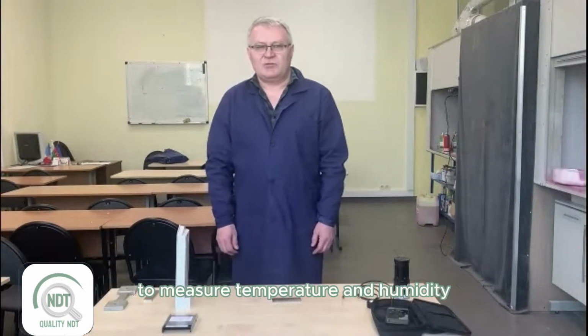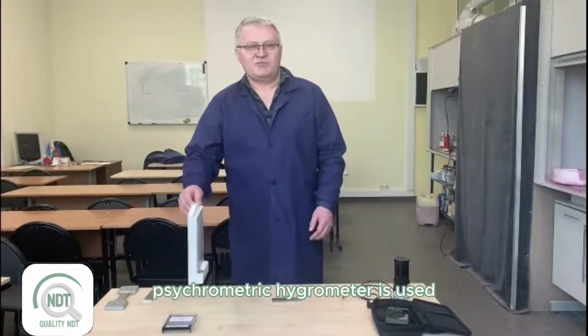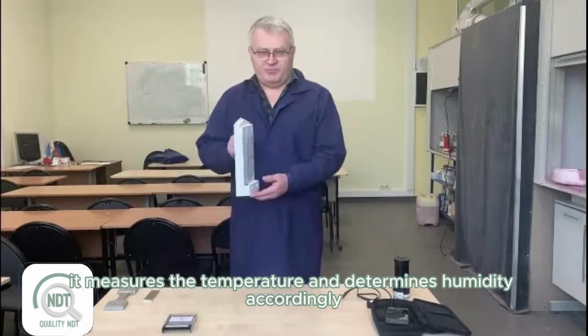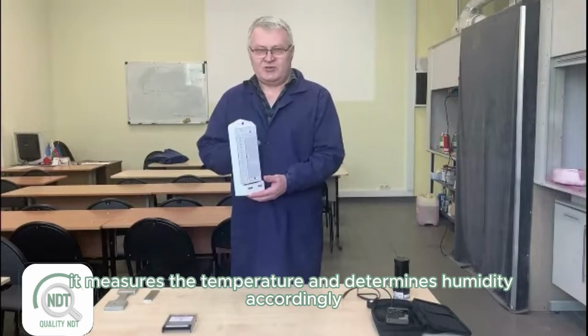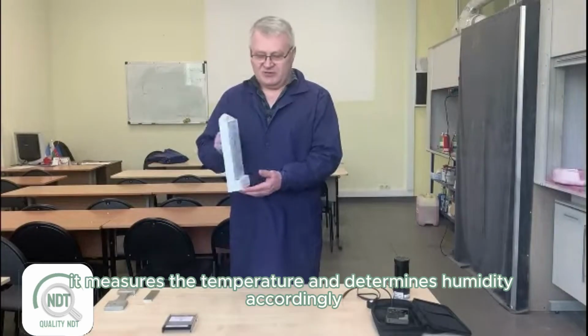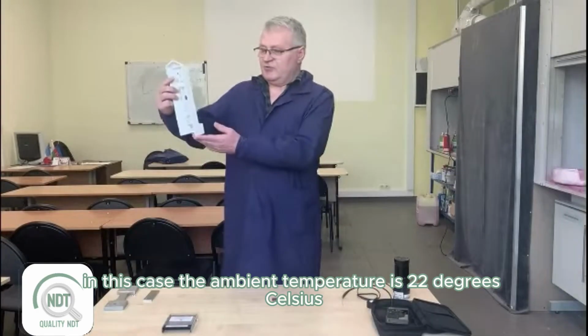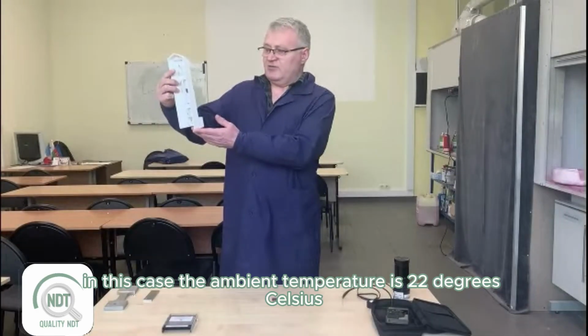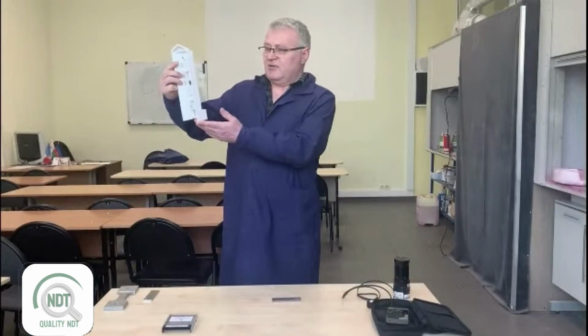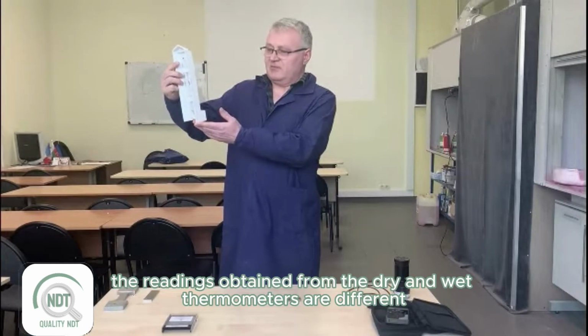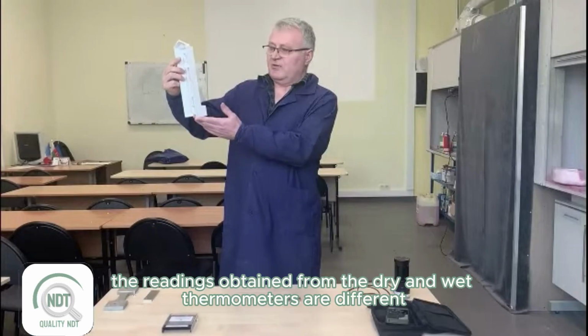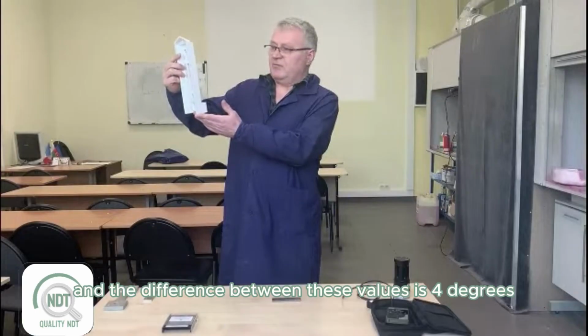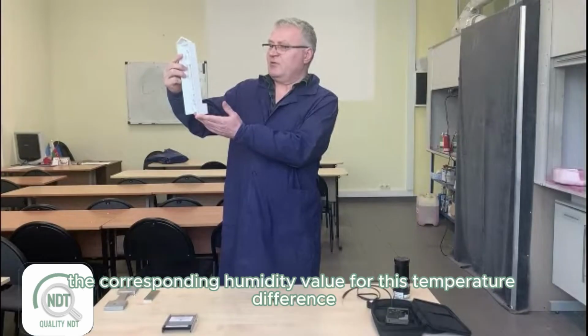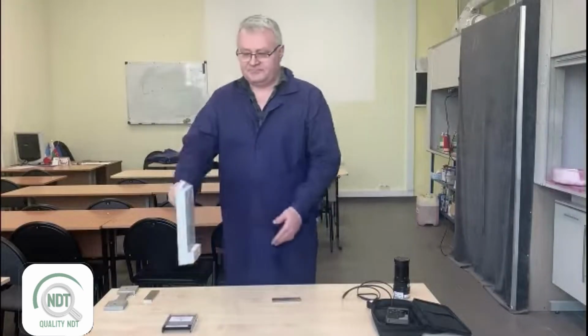To measure temperature and humidity, a psychrometric hygrometer is used. It measures the temperature and determines humidity accordingly. In this case, the ambient temperature is 22 degrees Celsius. The readings obtained from the dry and wet thermometers are different, and the difference between these values is 4 degrees. The corresponding humidity value for this temperature difference is 65%.